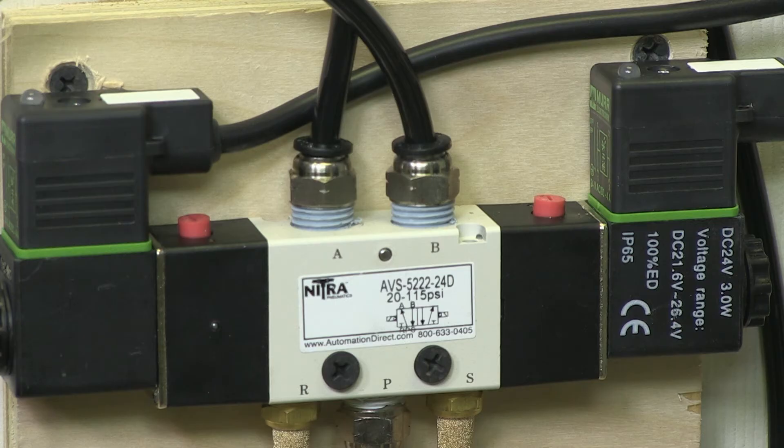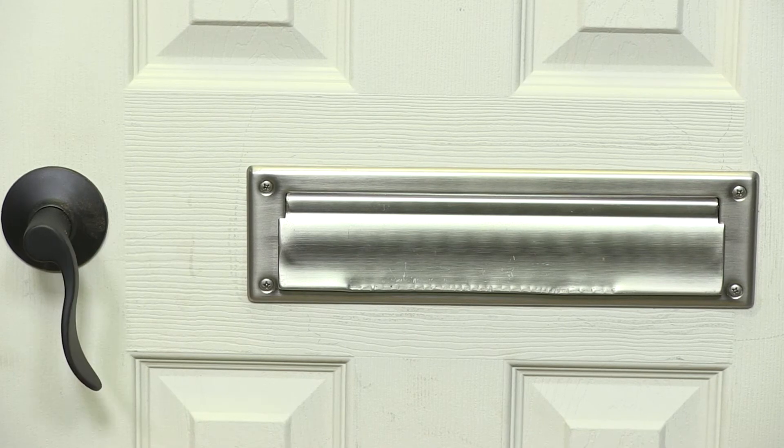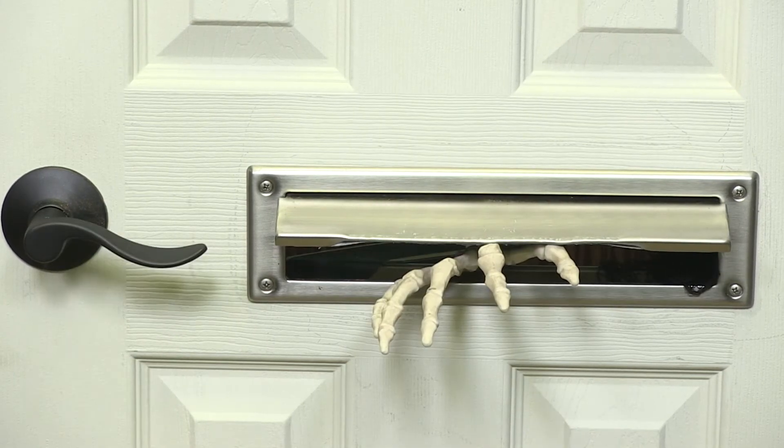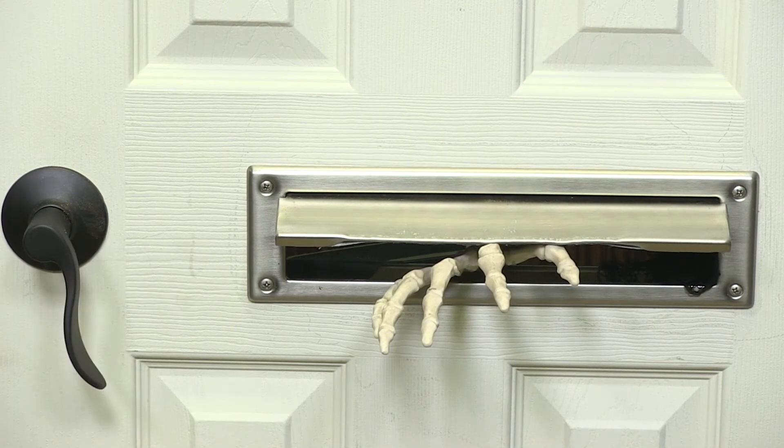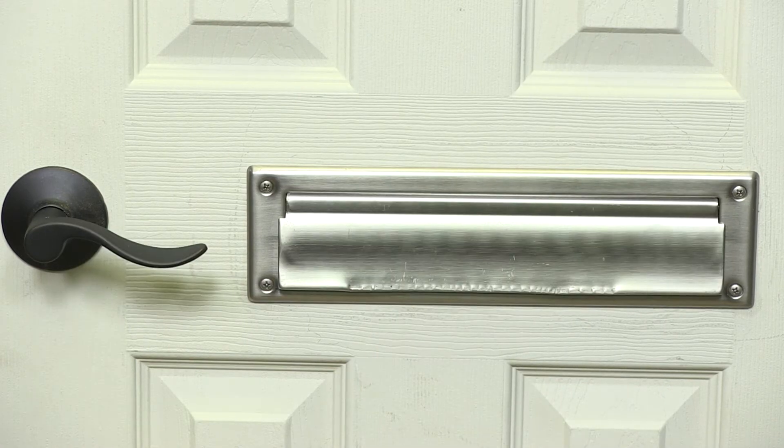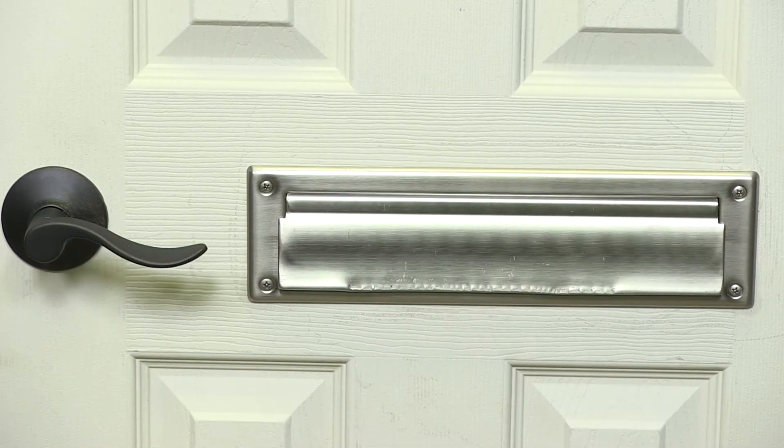We chose the four-way valve on the mail slot air cylinder so I can control the extension and retraction, and if we want to stop the hand somewhere in between full extension or retraction, we can. Otherwise I would have used a spring return solenoid which would have only allowed the cylinder to be at full extension or full retraction but nowhere in between.